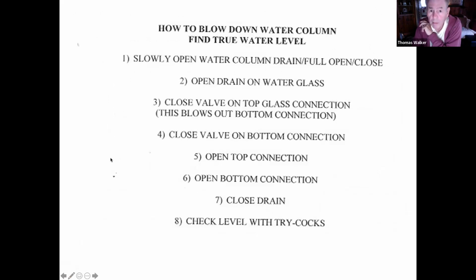And again, blowing down the water column and the gauge glass is known as finding the true water level. This needs to be done at the start of every watch that you take over. The inspectors love to hear that. And unless you plan on standing in front of the boiler the entire shift, this will guarantee to you that the boiler will trip if you get low water in it. That's what you want to know. Is that stuff going to work when I need it to? Does everybody kind of get that?